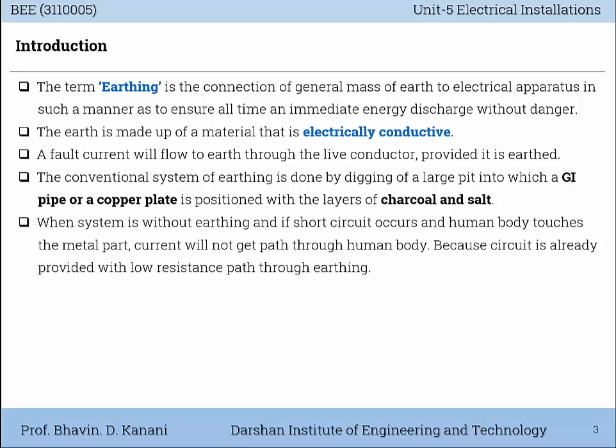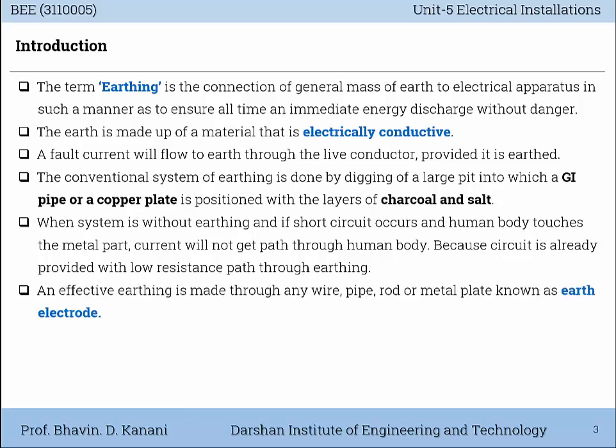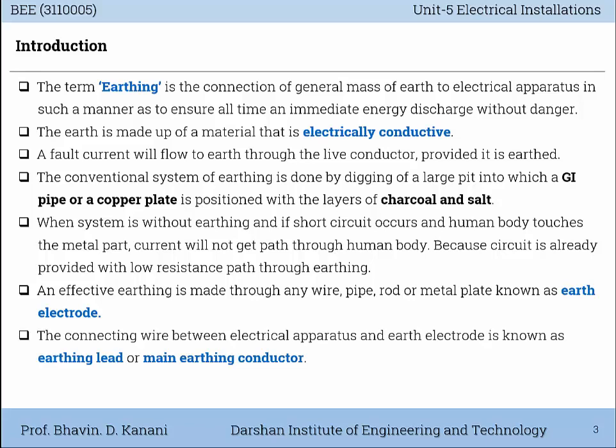When a system is without earthing and a short circuit occurs and the human body touches the metal part, the current will not get a path through the human body, because the circuit is already provided with a low resistance path through the earthing. An effective earthing is made through any wire, pipe, rod or metal plate, known as the earth electrode. The connecting wire between the electrical apparatus and the earth electrode is known as the earthing lead or main earthing conductor.